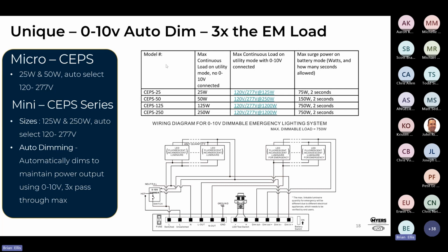So think about it: if you have a corridor and it wraps around some area, and let's say those are 3 lighting control areas, then what you would have is 3 of these micro or mini inverters. Then I'd ask, what's the wattage of my emergency lighting in that area? Okay, it's 500. Well, I can use the 250, in which case I would be at 50% light output, or I can use the 125, right? So it's really just a ratio of 125, or whatever the inverter rating is, divided by the emergency load.